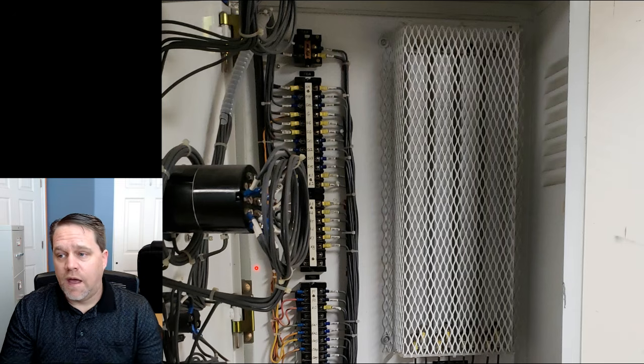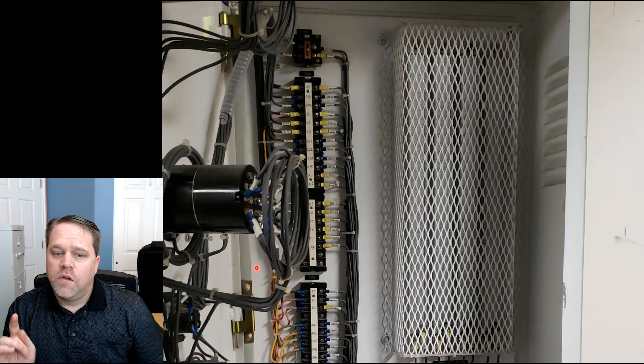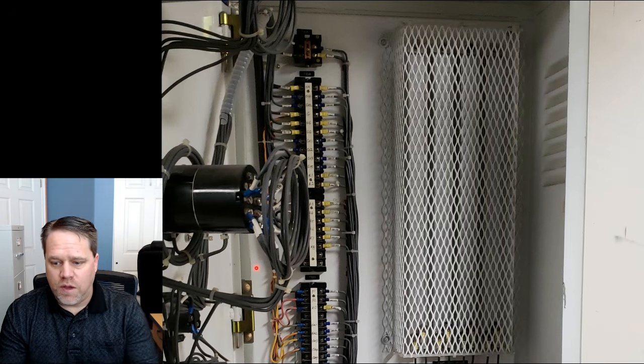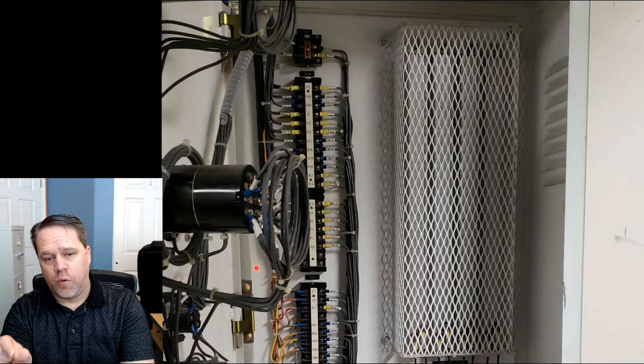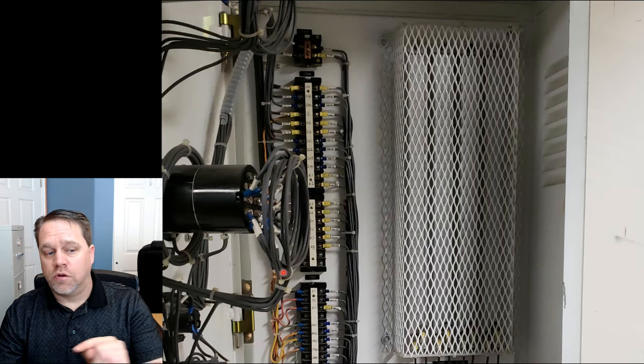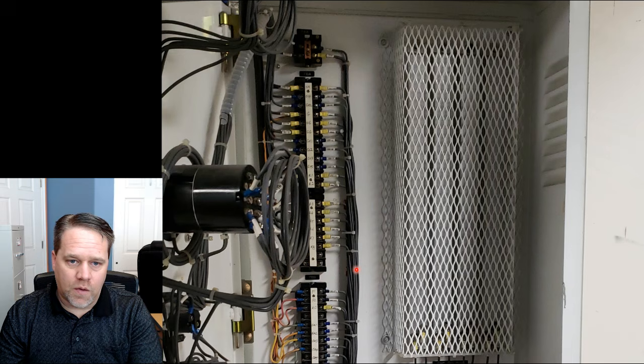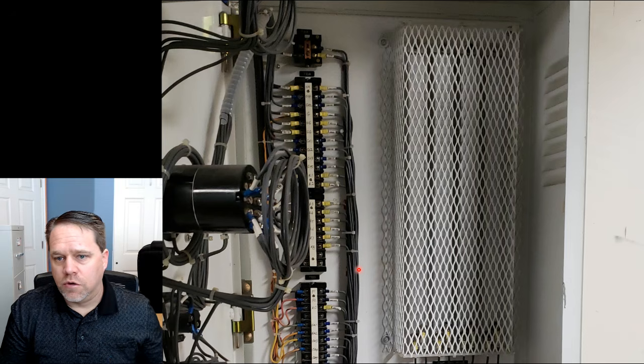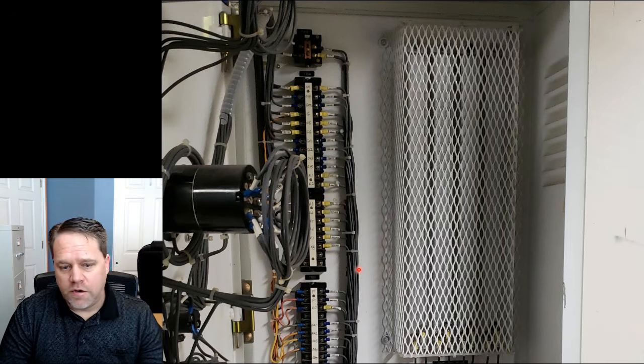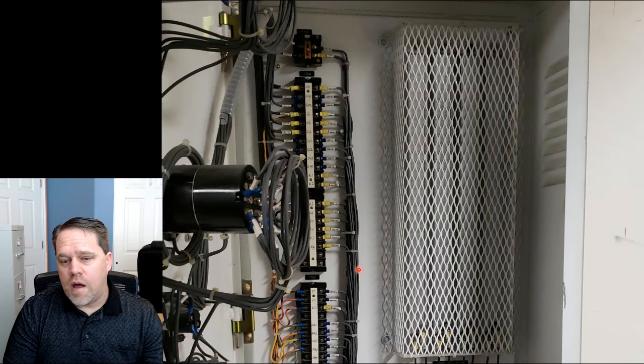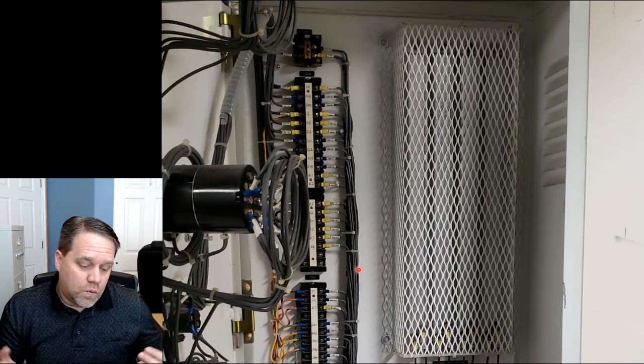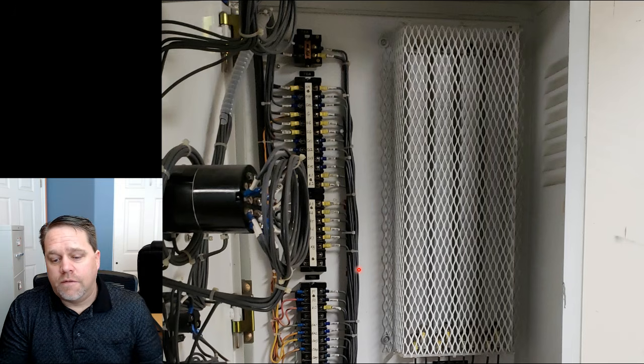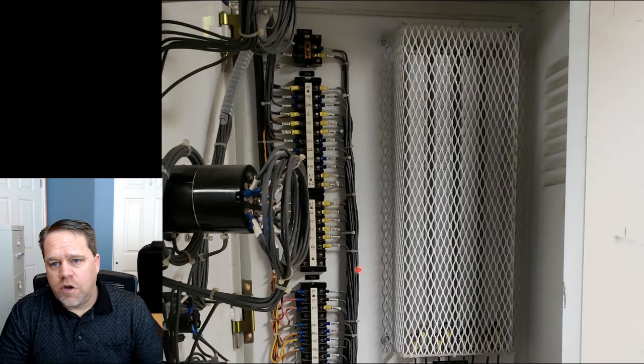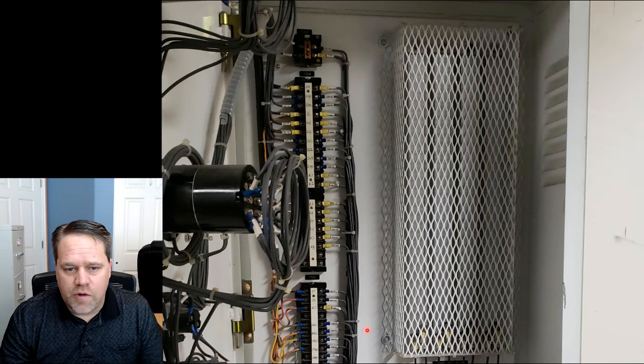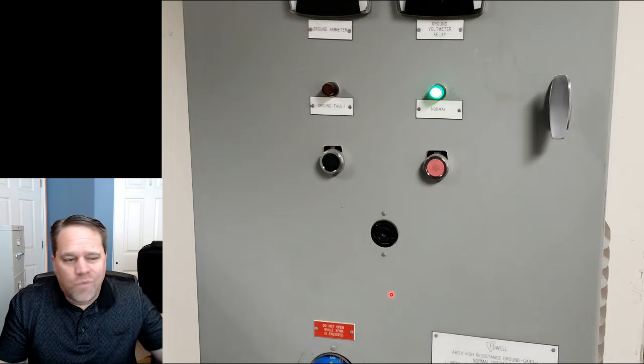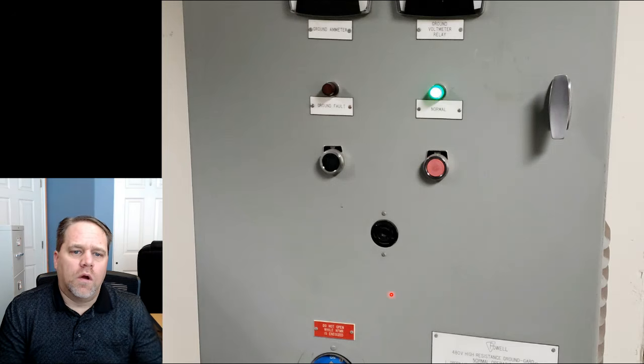So you don't get 277 out of this system. It's strictly for 480 volt loads. So you put this resistor basically between the earth, the grounding electrode conductor, and the XO point, the neutral point of the system. And because we don't have any neutral loads, we should never have any current going on that wire, right? Why would I have neutral current if there's no neutral loads? Well, the only reason that I would have current going on that conductor is if there was a ground fault. Now, if there's a ground fault on a system like this and it trips the breaker, it could be catastrophic. We could have a loss of life due to a ground fault. So instead of it tripping the breaker, we send that massive amount of current through this grounding resistor, and that limits the current to like 1 to 5 amps, something very, very low, where it would not initiate an overcurrent device.